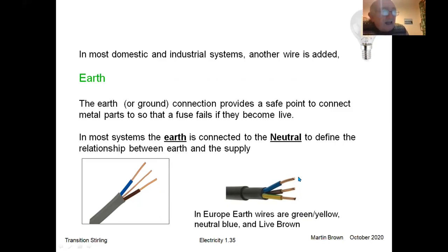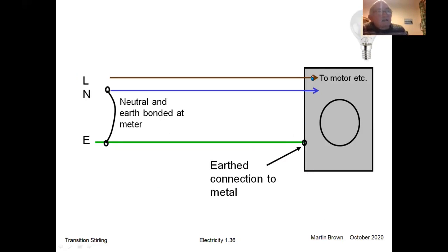Now, why have we done that? Well, let's look at a rather stylized washing machine or something here. We've now got three wires coming to it. We've got the live and neutral wire, which go to the motor, to the electronics, and all the stuff that's running inside the machine. We've now got an earth wire that's tied to the metal, okay? And we tied the neutral and the earth together. That's not something you do, that's something the electrician does when it's put together. There are slightly different ways of doing these things, but basically this is how it's done these days.